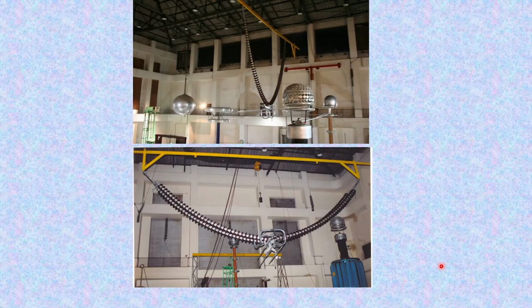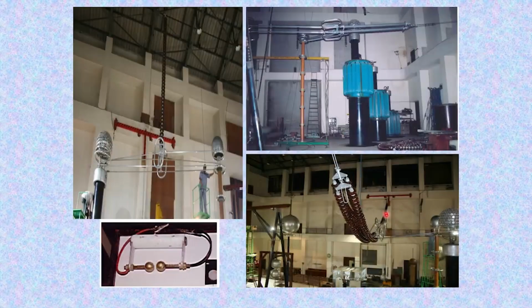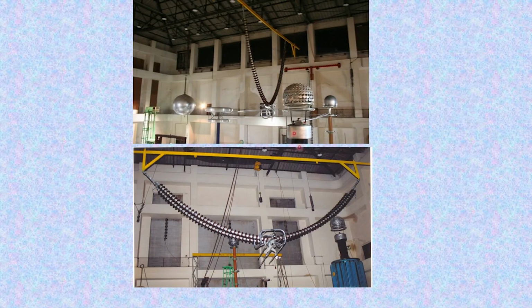So, this is again a different configuration. We have seen here the I suspension or a pilot string. We have a double tension arrangement similar to the field. We have a quadruple, that is a 4 insulator string, in the field. Here is a V configuration, single V configuration, and this is a double V configuration. So, these are most of the configurations which you normally encounter at high and very high voltage levels. So, you see, similar configurations have to be arranged.